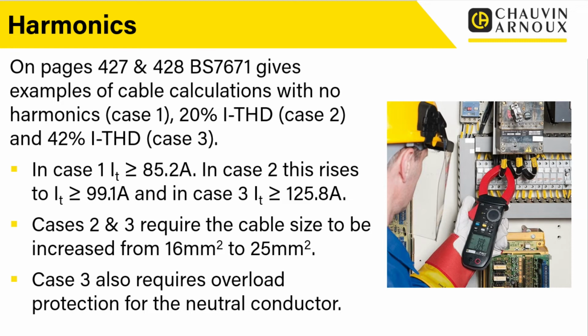So if we start off in case 1 where there's no harmonics, they calculate that we need a cable that will carry at least 85.2 amps. Whereas if we add in 20% current harmonics, that rises from 85.2 up to 99.1. And then if we take that up again to 42% THD, we're then up to 125.8 amps. So again, you can see there's quite a spread there depending on the effects. Now, when we look back at the example installation we said we were talking between 15 maybe to 20. So you can see there can be quite a difference in there when we start looking at installations and the figures that we should be applying.